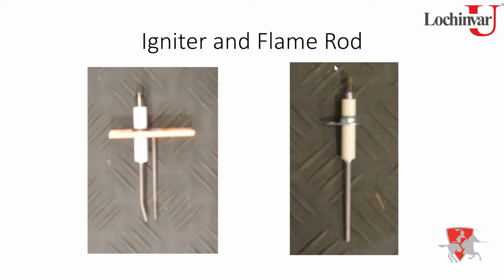Now, as far as rods and igniters go, some people will just replace them as part of their annual maintenance. And if you want to do that, be my guest. That's totally up to you. All right. But realistically, you don't need to replace the rods unless they are physically damaged. So unless the rod is burned off to where it's no longer sitting in the flame or the insulator's cracked or something like that, there's really no reason to replace the rod. If they're dirty, clean them up.